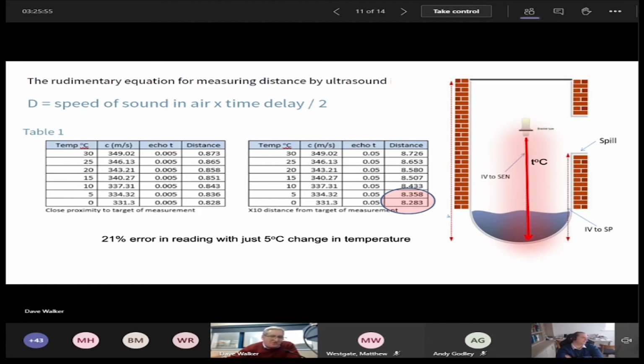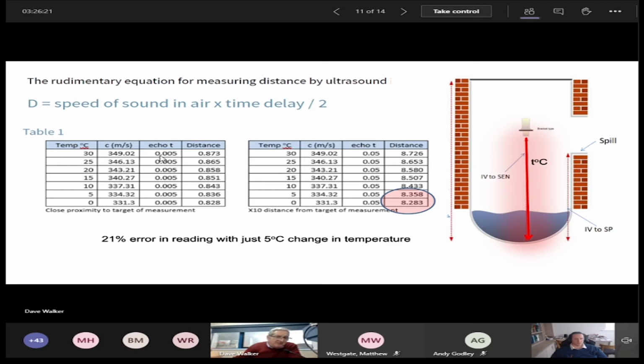Temperature, I just touched on it slightly there, but you can see here that just a 5 degrees change in temperature, the table on the right being an 8 meter transmission, gives a 75 millimeter error in the target measurement. The same 5 degrees centigrade error on the left, if you're within 800 millimeters of measurement, gives an actual error in level reading that is much less. Now, temperature is something we are all well aware of, and we do some very clever adjustments within the circuitry within the ultrasonic sensors out there in the market. But when you're at such a distance of 8 meters, if you're monitoring the temperature in close proximity to the actual ultrasonic sensor, to actually know the actual change in temperature throughout that column of air, i.e.